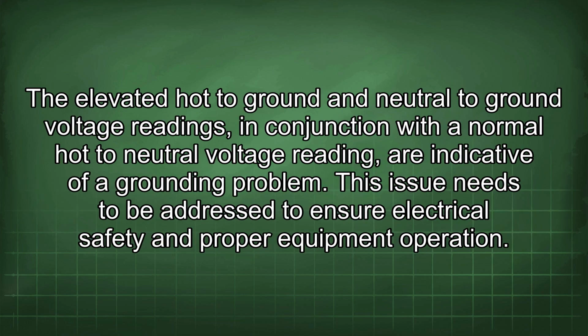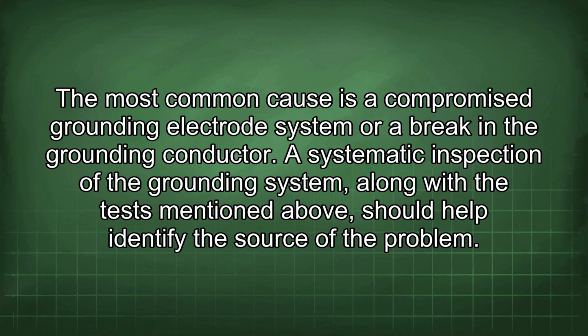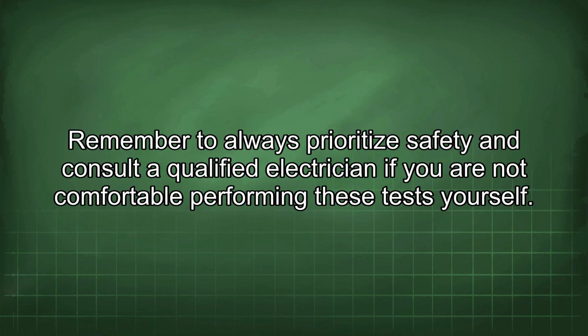The elevated hot to ground and neutral to ground voltage readings in conjunction with the normal hot to neutral voltage reading are indicative of a grounding problem. This issue needs to be addressed to ensure electrical safety and proper equipment operation. The most common cause is a compromised grounding electrode system or a break in the grounding conductor. A systematic inspection of the grounding system along with the tests mentioned above should help identify the source of the problem. Remember to always prioritize safety and consult a qualified electrician if you are not comfortable performing these tests yourself.